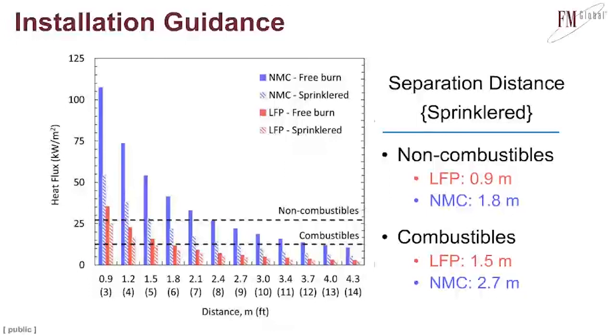Now you can do the same thing looking at the sprinkler data. For the NMC sprinkler, which is the purple and white stripe lines, you can see that you cross the threshold value for non-combustibles around 6 feet, and you cross for combustibles at 9 feet. So the act of adding sprinklers means that combustibles could be moved from 13 feet away to 9 feet away. You can get closer and closer, and the numbers look better as you go back to the iron phosphate, the LFP systems, because the total peak heat release rate was lower.